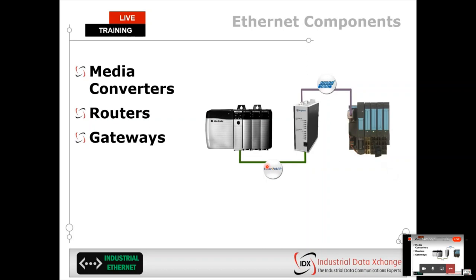Gateways become very useful. I got a question recently from the PROFIBUS discussion we had last week: an engineer asked how to connect PROFINET to PROFIBUS. PROFINET runs much faster, around 100 megabits per second, while PROFIBUS runs slower, from 9600 bits per second up to about 12 megabits per second. He asked if they were directly relatable, or if he just needed a device to slow down or buffer PROFIBUS messages. Not really—they're two completely different languages or protocols, not the same at all. So you get gateways that can convert serial-based protocols like PROFIBUS and connect them to high-level Ethernet-based protocols.